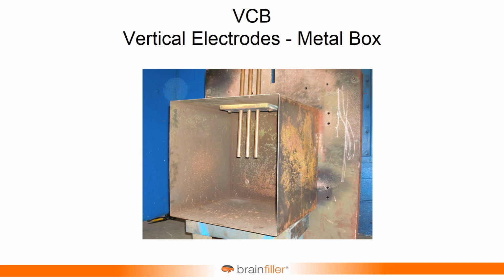And so then when you close the breaker and you're closing into a short circuit, that wire vaporizes, and then the arc is established, and it runs away from the supply, and the energy comes off the tips. And what it'll do is it'll go down and then spill out of the box off of the end of the tips.